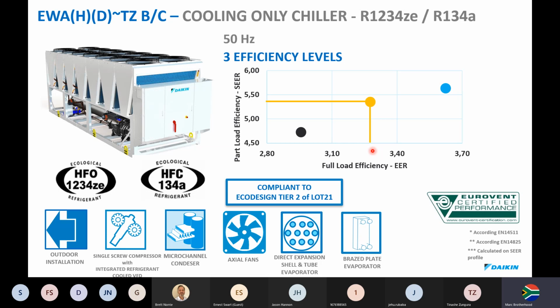You give yourself 30%. You size the chiller 30% over capacity, because as we said earlier, 97% of the time the chiller is going to run in the sweet spot when the compressor's unloaded, and that's where it's going to surpass any other non-inverter chiller. The silver, gold, and platinum option is merely the size of the chiller. So if I wanted to go platinum to give myself seasonal energy efficiency of about 5.8, I'd possibly have half a V block installed further to just give me that extra heat rejection.